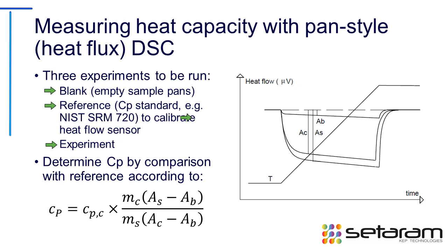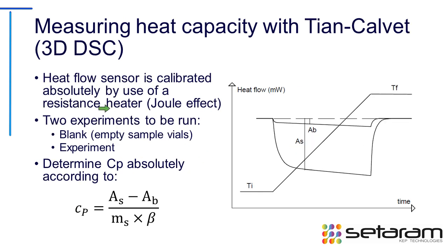But what's an advantage with 3D is that we only have to run 2 experiments. We only have to run the blank versus the experimentation. This is because the heat flow sensor is calibrated at factory, and it's calibrated to be absolutely relevant due to the resistance heater or the Joule effect.